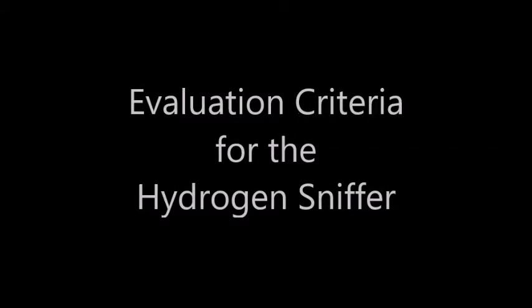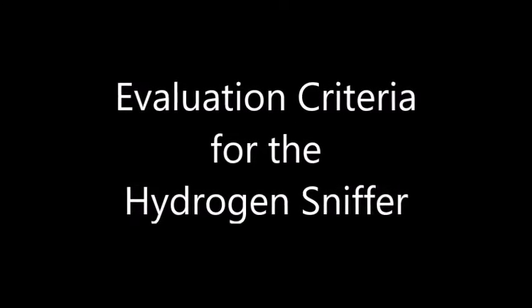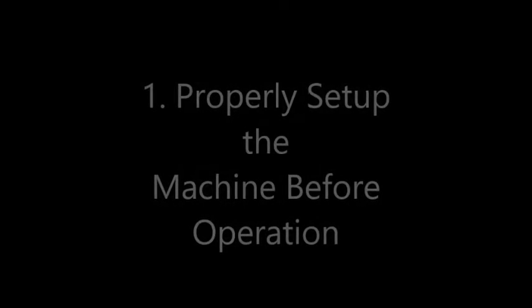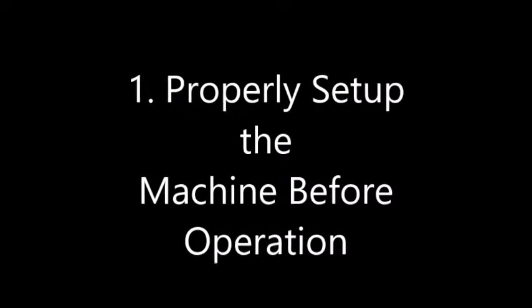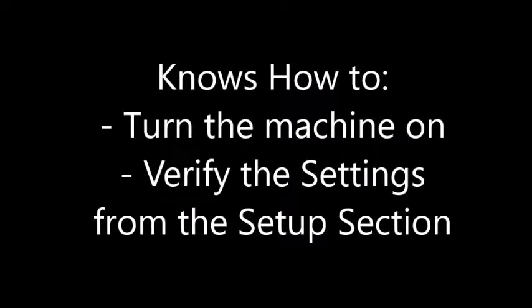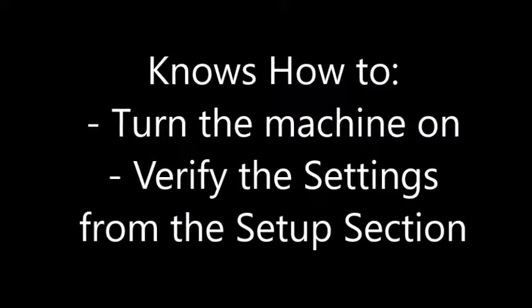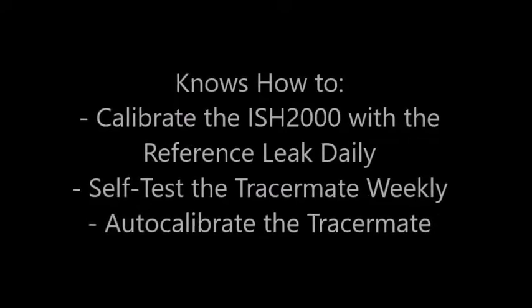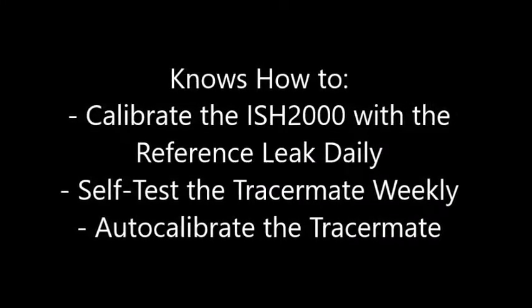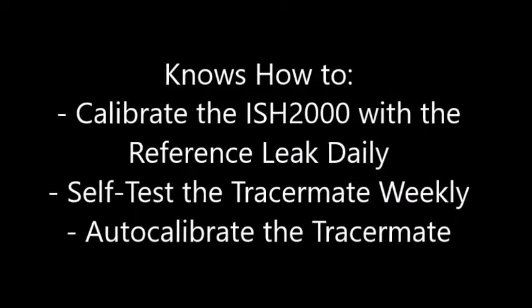Before we're done, let's go over some evaluation criteria on operating the hydrogen sniffer. Number 1. The operator is able to properly set up the machine prior to operation, so the operator knows how to turn the machine on and verify the settings outlined in the setup section. Number 2. The operator can successfully calibrate and operate the testers according to the instructions above. To do this, the operator will have to know how to calibrate the ISH 2000 daily with the reference leak, self-test the Tracermate weekly, and auto-calibrate the Tracermate for new parts.